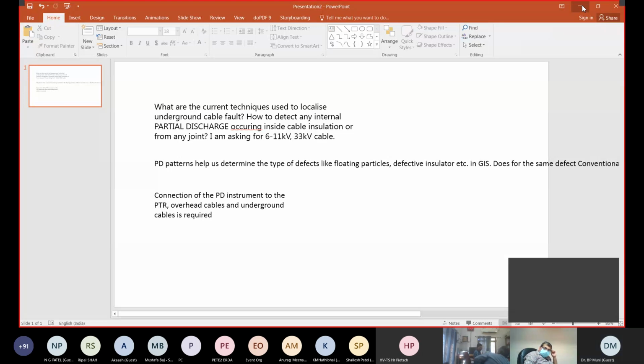For on-site commissioning tests, it's automatically included in the standards, because any voltage stress higher than the operating voltage consumes a little bit of the life of the equipment. That's the point, I guess, you mentioned. So if you'd like to do monitoring, you have to ask the utility and the supplier of the equipment if you're allowed to apply a higher voltage for PD monitoring, also after repair, rather than just the normal operating stress, because this is exactly your point. You're only allowed to apply the normal rated voltage and measure the PD. Be careful if the system has been under operation for several years before applying a higher voltage stress than rated. You have to ask the supplier or the utility if it's allowed.